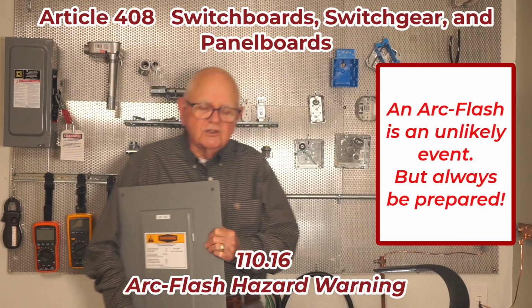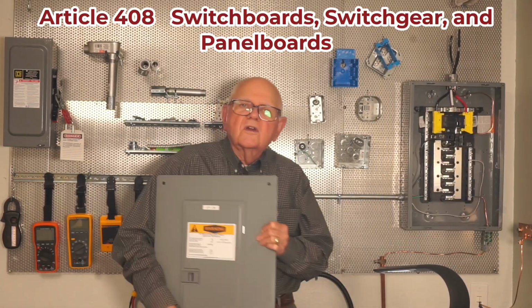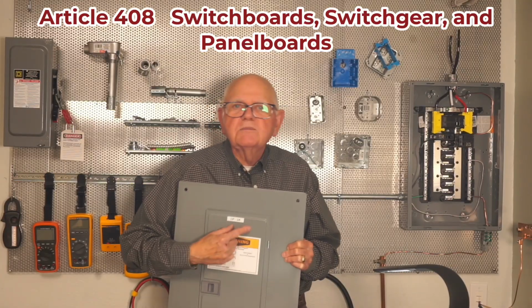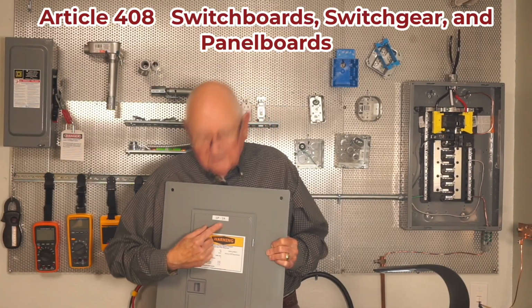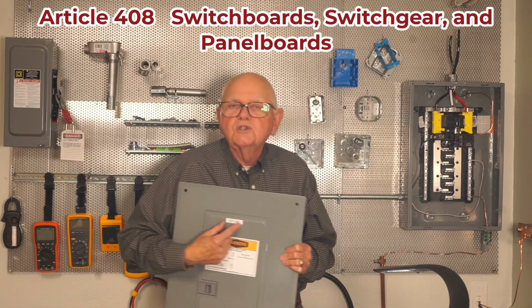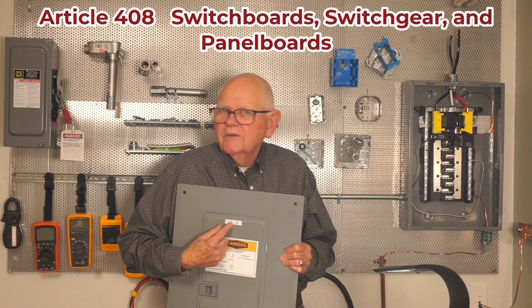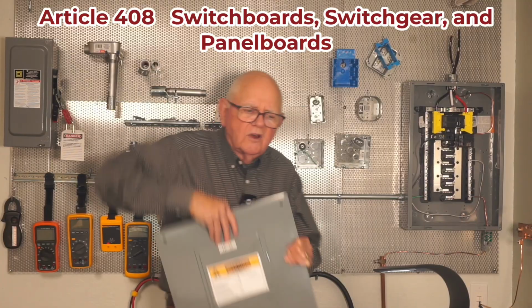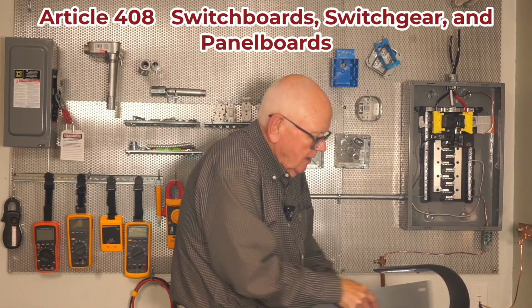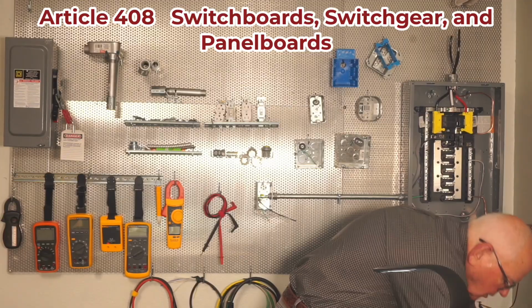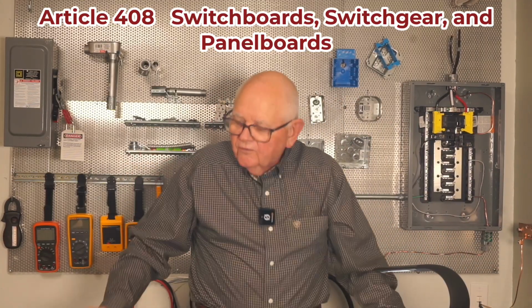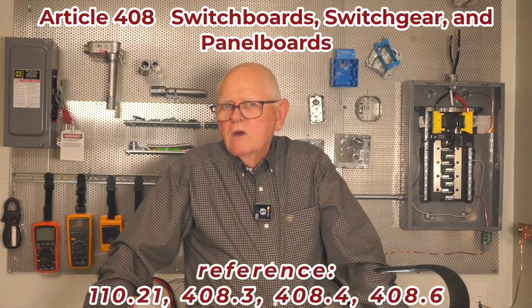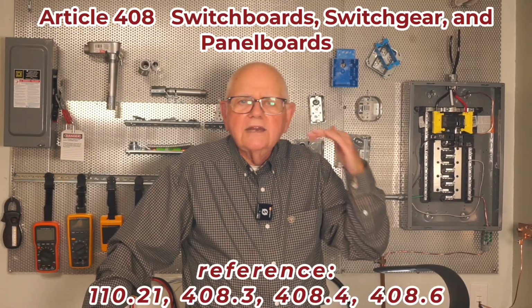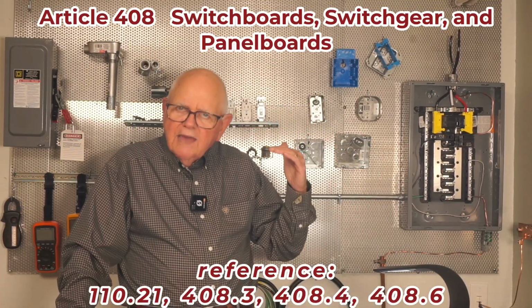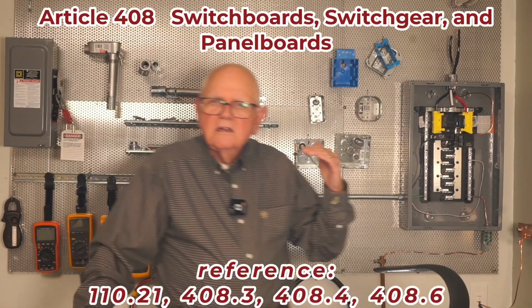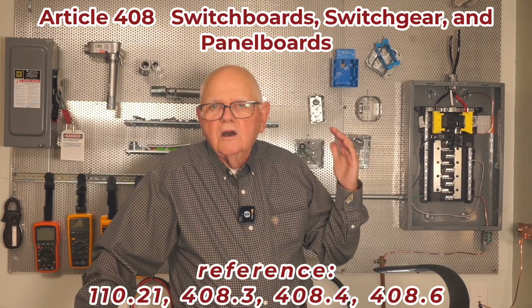That's going to protect us. As we go through and talk about the markings on our panel boards, this is just a piece of label tape put on here that tells us this is LP2A or whatever it says. That's generally not good enough. If we look through the requirements for panel board markings that we're going to find in 408 and 110 and so forth, the general requirements talk about any marking that I put on the cover of that cabinet, cutout box or whatever cover I put on that panel board.